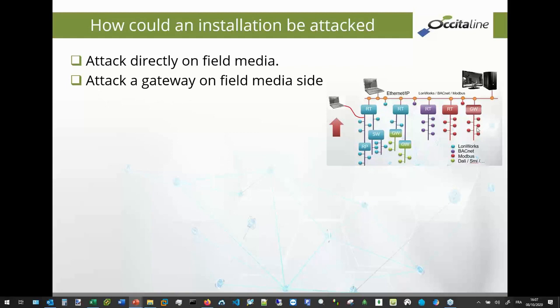How could an installation be attacked? In many ways. First, you can connect a computer directly on the field. If it's LON, BACnet, Modbus, or whatever you want, the attack can arrive directly on this field medium. For protecting against that, you have just one thing: hide the cable and hide any device. It's not easy.